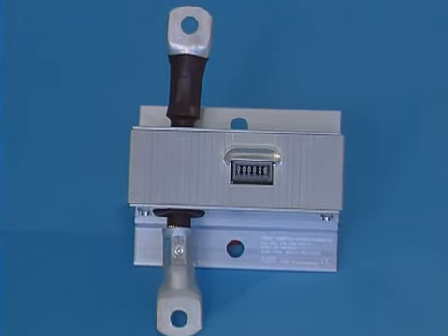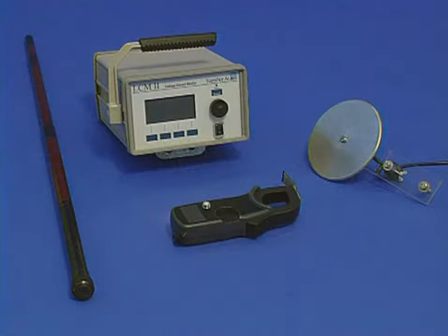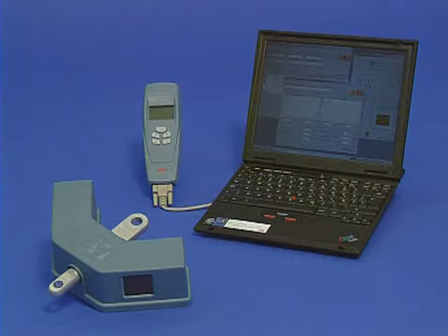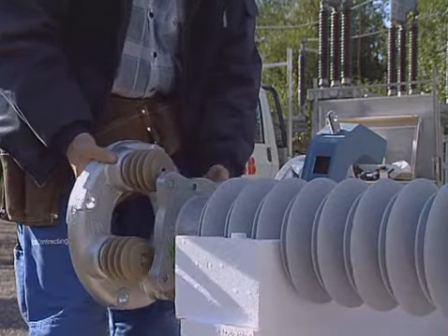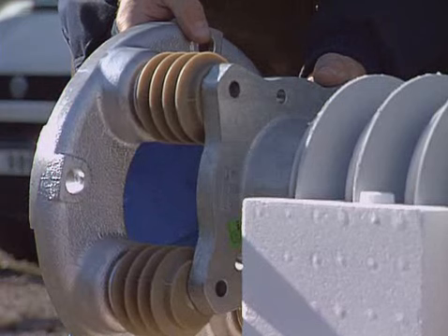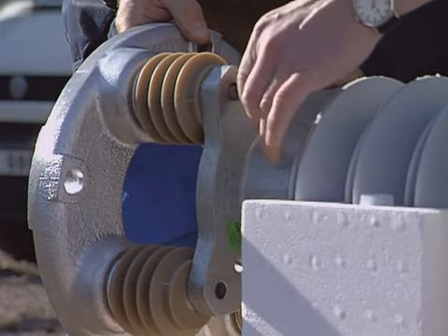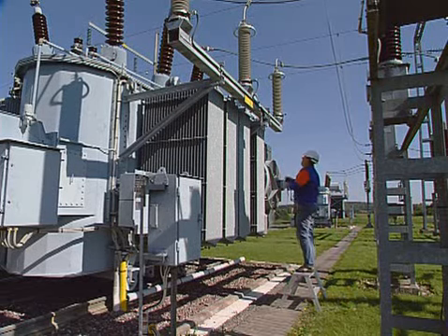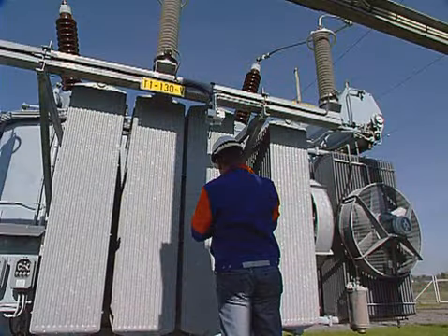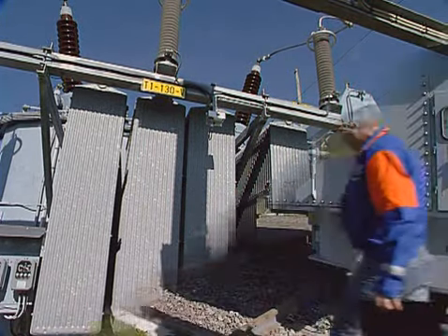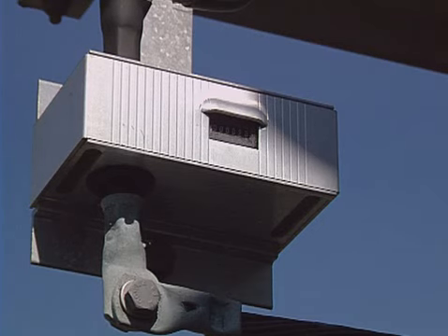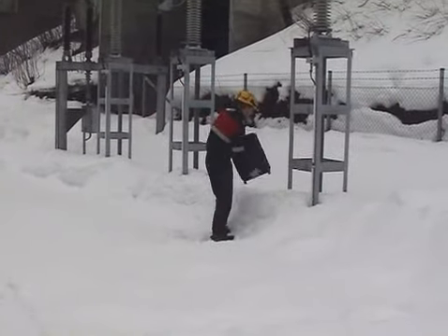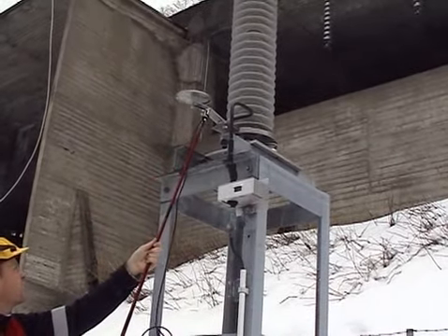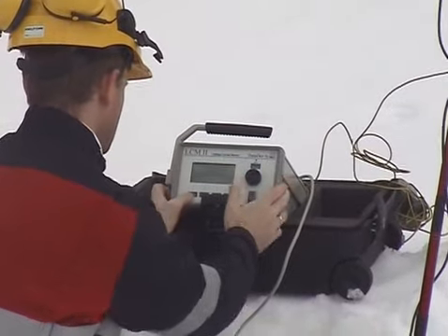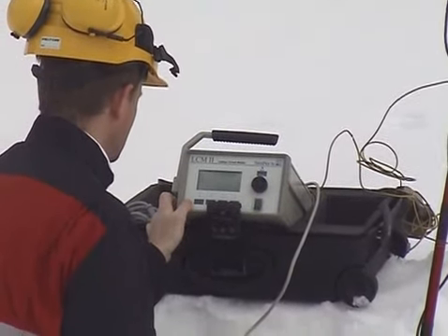ABB's range of measuring instruments includes the X-Count-A surge counter, the LCM2 leakage current monitor, and the X-Count-2 monitoring system. Regardless of which measuring instrument you choose, the surge arrestor must be equipped with an insulated base in order to ensure it is insulated from earth. The surge counter X-Count-A provides information on how often the arrestor has been in function. It can be applied to all types of gapless metal oxide arresters. The portable leakage current monitor LCM2 can be used to measure the resistive leakage current through the arrestor. This measurement method is best suited for existing facilities.